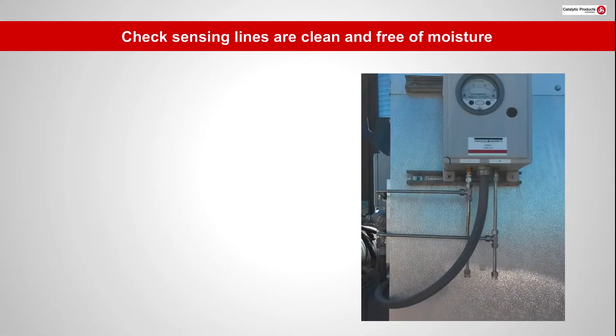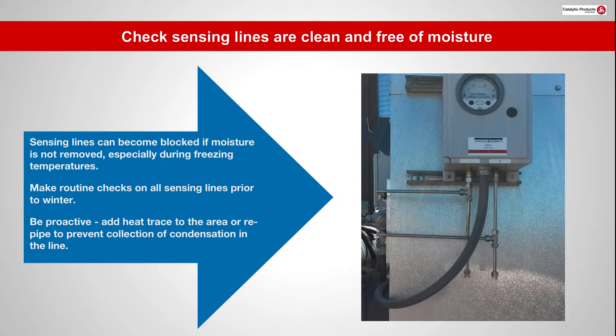Sensing lines can become blocked if moisture is not removed, especially during freezing temperatures. Make routine checks on all sensing lines prior to winter. Be proactive — add heat trace to the area or re-pipe to prevent collection of condensation in the line.